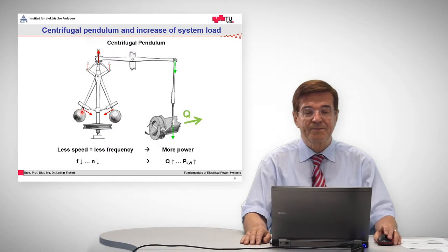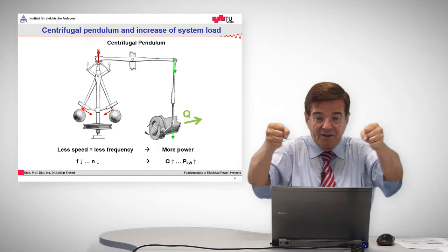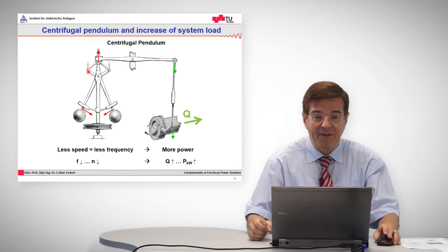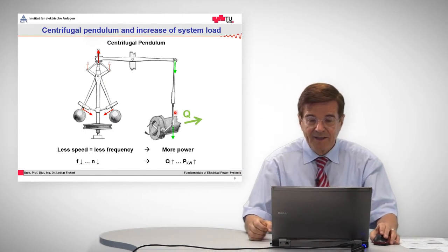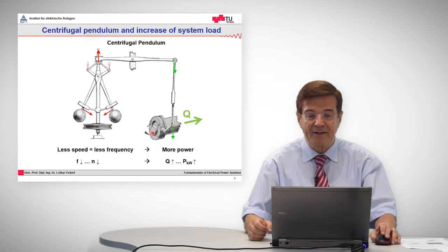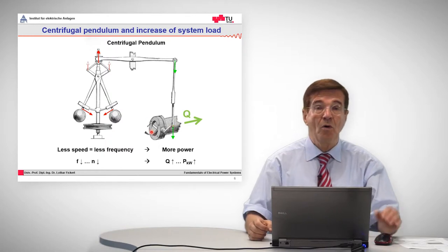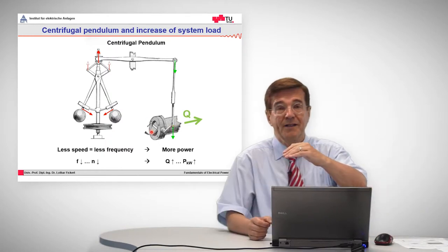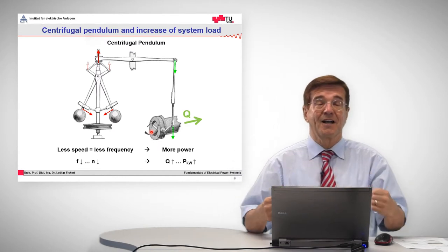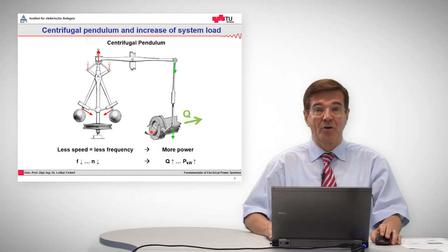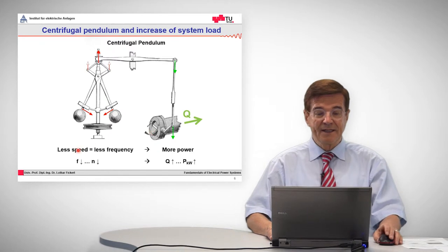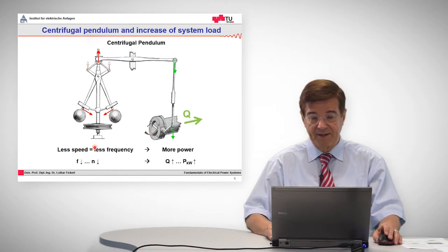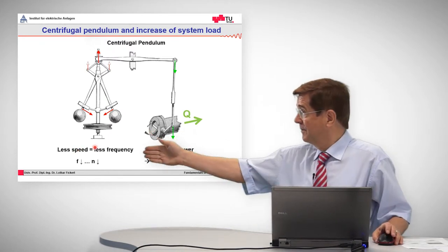And what happens here? In this pendulum, when it slows down, the balls will come together. And by way of this lever mechanism, it opens in the same way this throttle valve, more water goes through the turbine, and the turbine takes up speed and puts out more power. And that means less speed means less frequency. And that means more power.